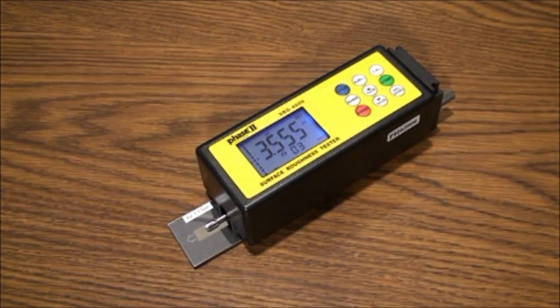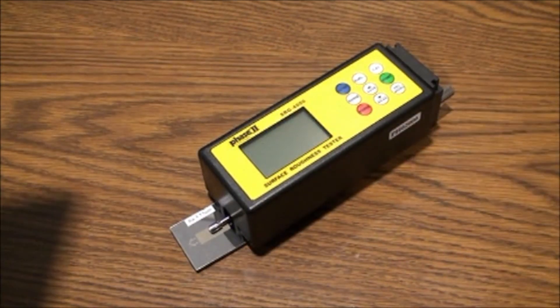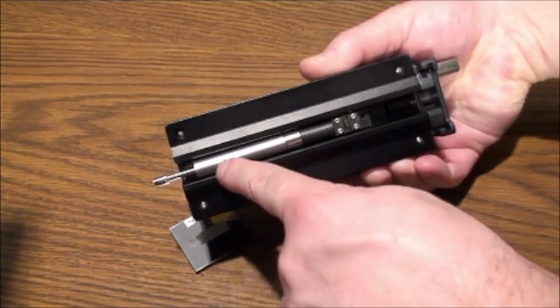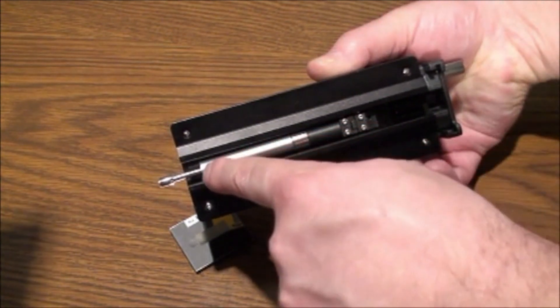As you can see, the SRG-4000 is a handheld battery-powered instrument with a graphic display and controls on top and an extended stylus, which will extend and retract upon taking surface roughness samples automatically. To begin, insert the stylus that is supplied in a separate container for optimum protection. Make certain to line up the plug and press easily into the socket.